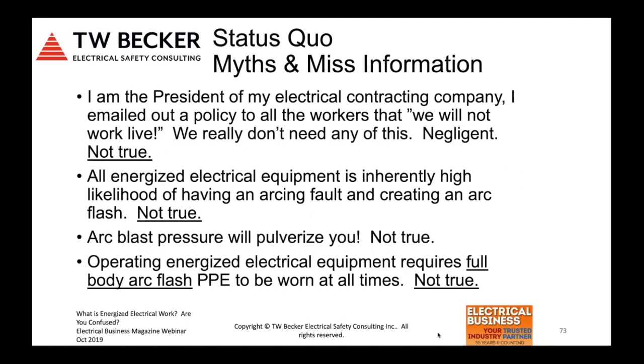So more of the myths. I'm the president of the company. I sent a policy to all the electricians: we don't work energized, we really don't need any of this. That's actually a negligent statement because every journeyman electrician owns a digital multimeter and does energized electrical work. All energized electrical equipment is inherently high likelihood of having an arcing fault and arc flash being created on it. I believe that's not true. It isn't 100% probability that an arcing fault and arc flash occurs on energized electrical equipment. We have to have an abnormal condition. Arc blast pressure will pulverize you. It's not true.